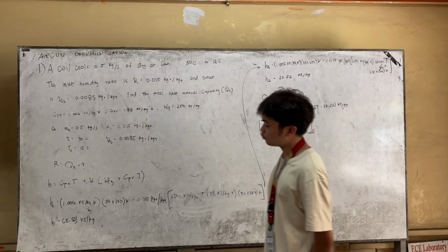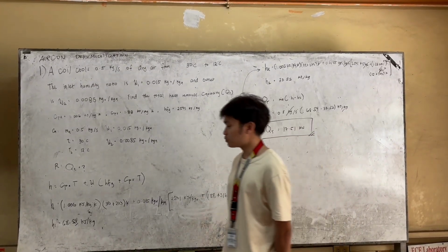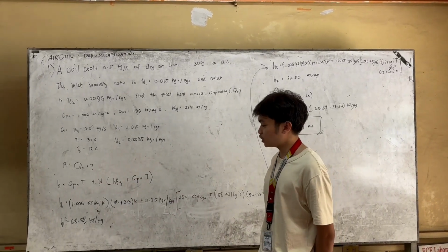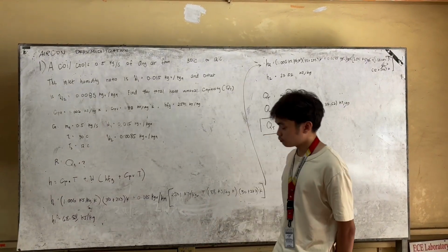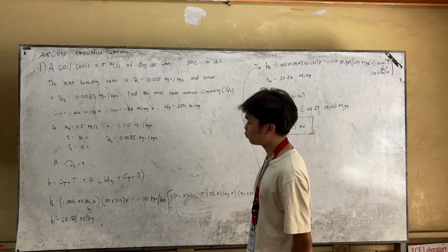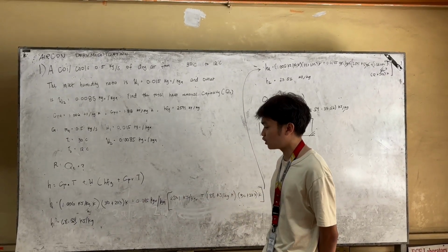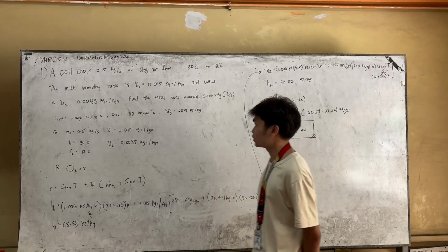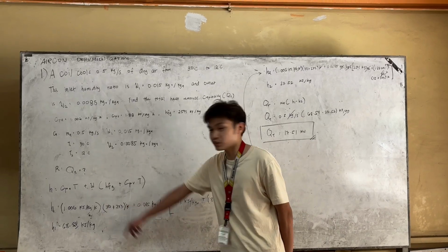The following formula we'll be using first to get enthalpy is Cpa times T plus your humidity ratio times HFG plus Cp of the vapor times your temperature. So for enthalpy 1, we only need to plug in the values. We have the Cp, which is 1.006 kilojoules per kilogram Kelvin, times 30, which is the state 1, 30 degrees Celsius, plus 273, since the value is in Kelvin.